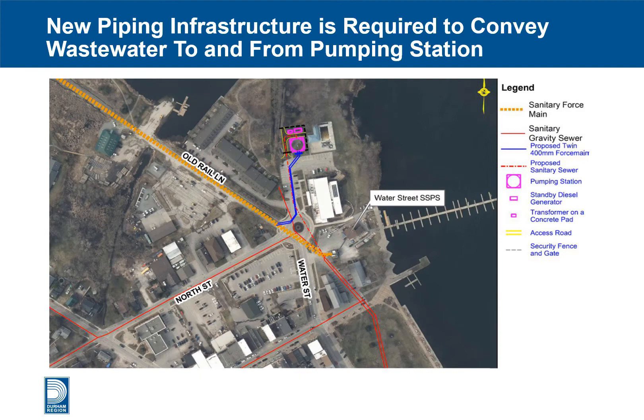New piping infrastructure is required to convey wastewater to and from the pumping station. The existing sanitary force mains are located on Old Rail Lane and connect to the existing Water Street station, as shown in orange hatched lines. Twin 400 mm diameter force mains are proposed to connect the new pumping station to the existing force mains. An inlet sanitary sewer will connect the existing maintenance hole upstream of the current station on Water Street to the new pumping station wetwell, outlined in red hatched lines. The station will also include a standby generator and transformer outside the building, a new access road, and a gate and fence around the property.